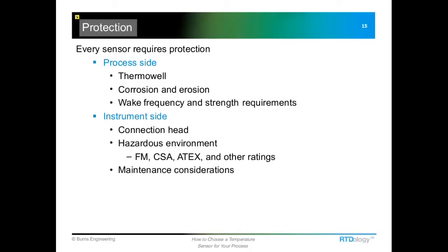On the outside, we said we had an explosive gas, so we're going to have to look at an assembly that is rated for those types of atmospheres. And then finally, how do we maintain this probe? What's the easiest way to pull it out to calibrate or replace, and still maintain all of the hazardous environment ratings?